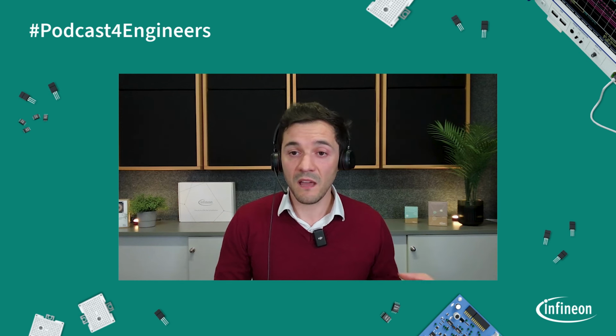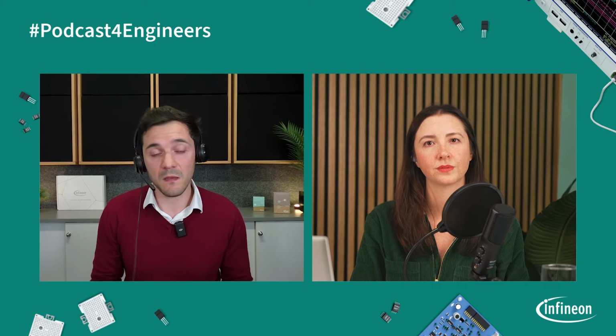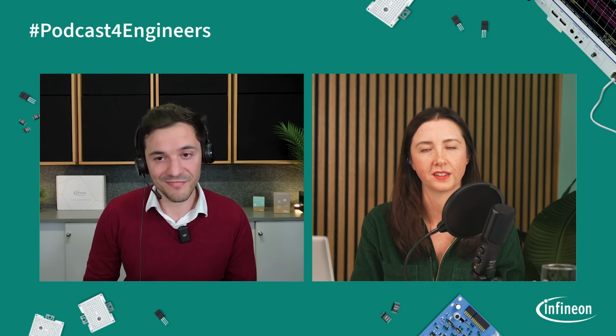So think about it: you process 80% of the energy through an unregulated converter, and then through a regulated converter, you process only 20% of the energy. Sounds efficient because you are basically having one converter which is not very efficient, but is processing just 20% of the power, meaning you can increase power density, efficiency, and eventually you can also keep up with this high current trend. Okay, so that was the regulated side of things.